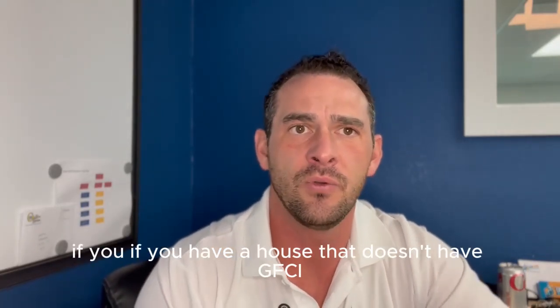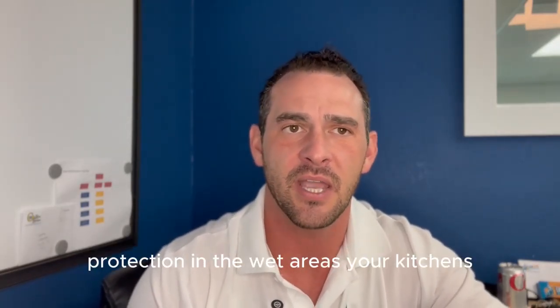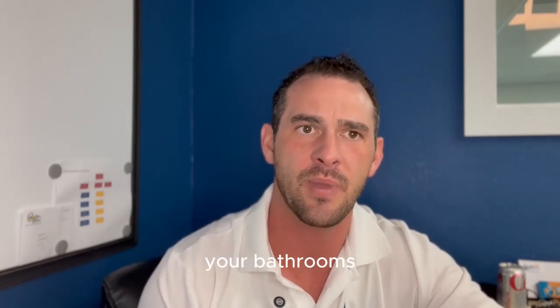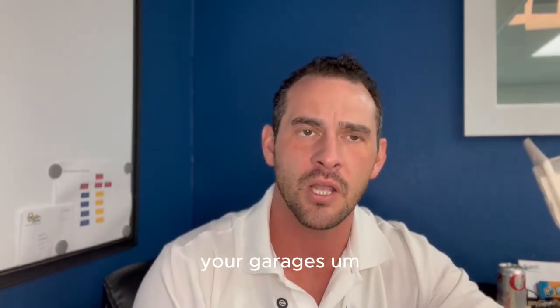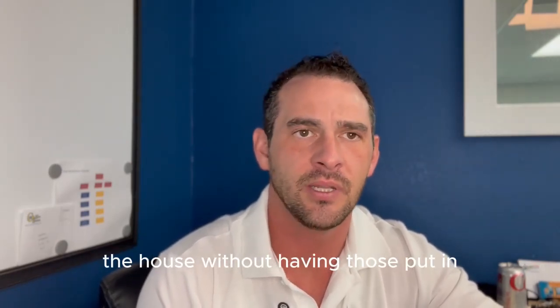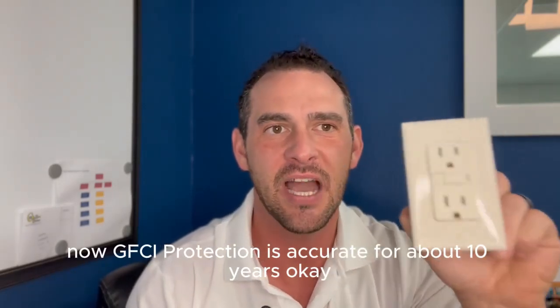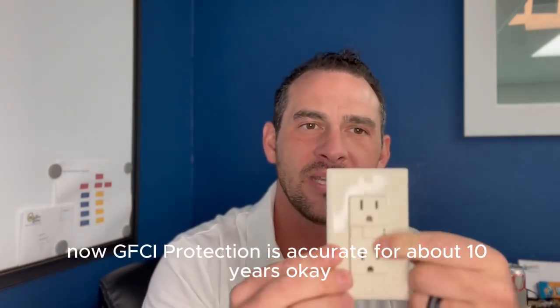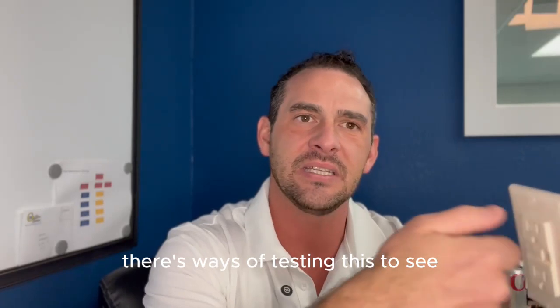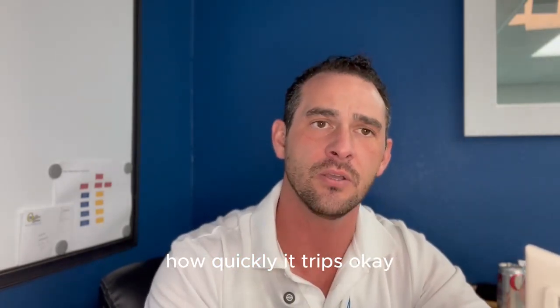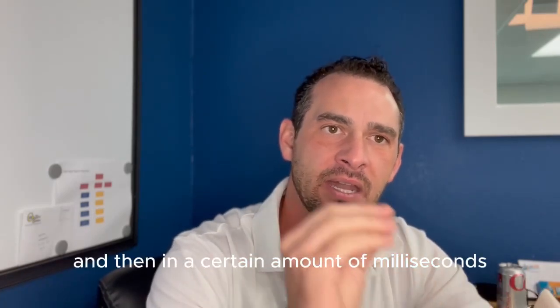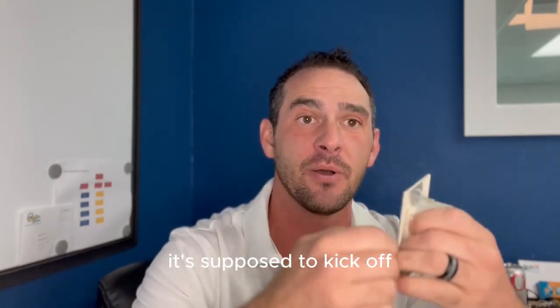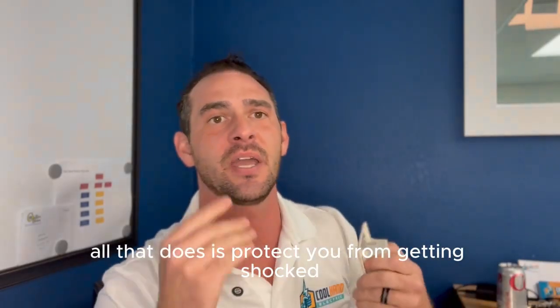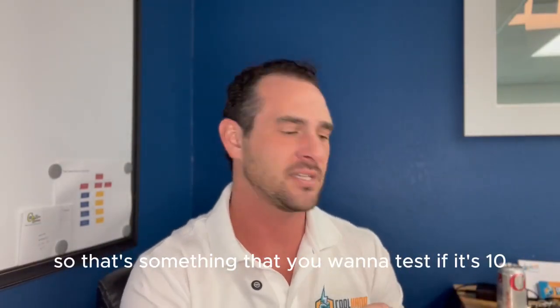If you have a house that doesn't have GFCI protection in the wet areas, your kitchens, your bathrooms, your exterior, your garages, you're not going to be able to sell the house without having those put in. It's just a basic thing. Now, GFCI protection is accurate for about 10 years. There are ways of testing this to see how quickly it trips. A certain amount of milliamps is given to it, and in a certain amount of milliseconds it's supposed to kick off. All that does is protect you from getting shocked. So that's something that you want to test.